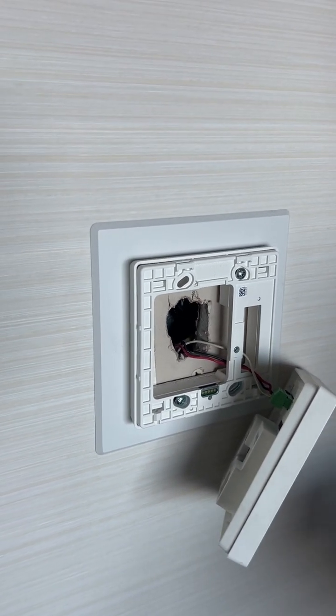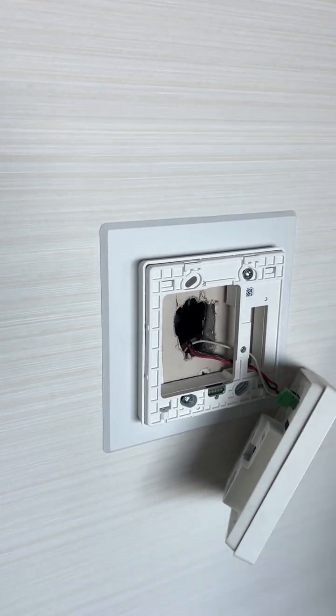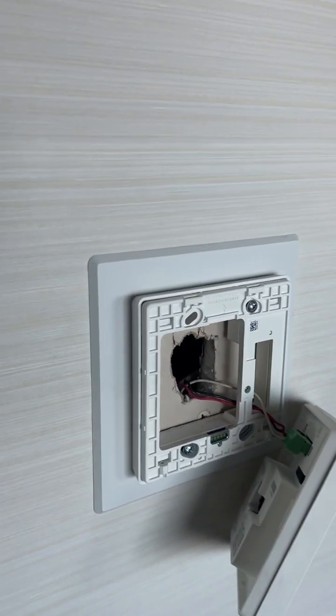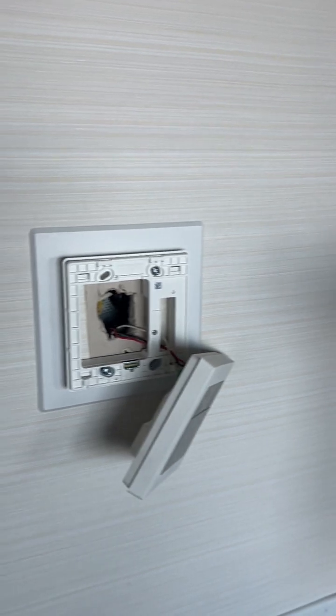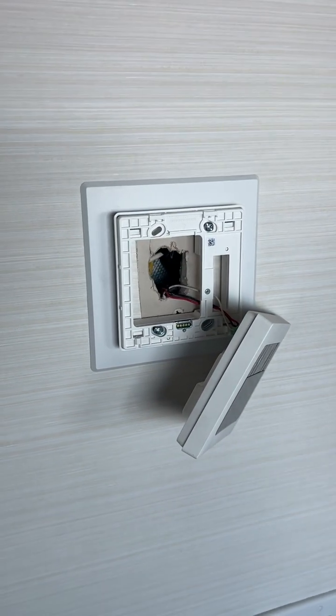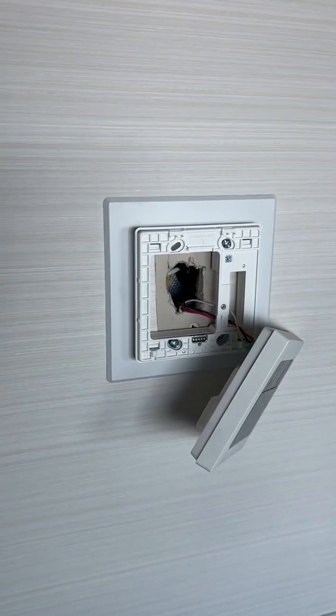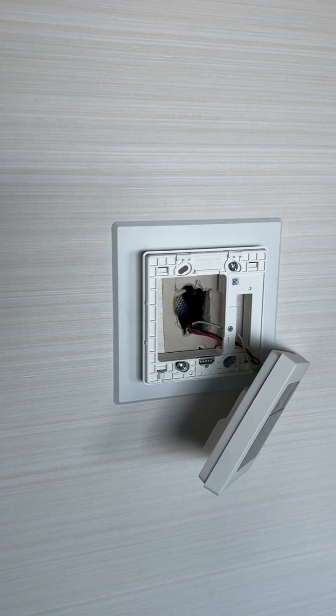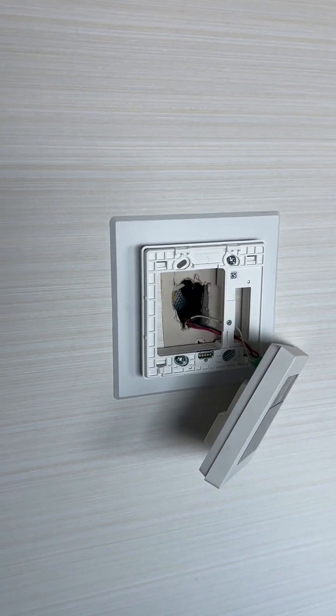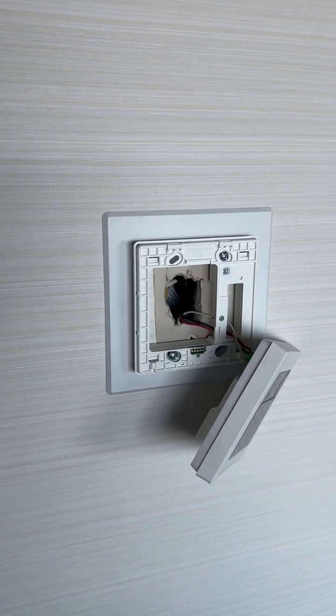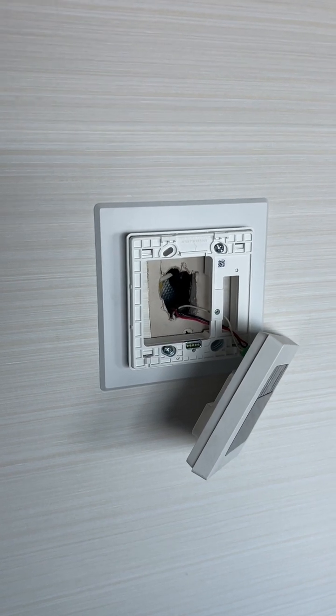Door switches and balconies, all of that - the lock you would need to rebind, because they share MAC addresses. So if you physically replace the thermostat, it doesn't have that information anymore between the lock and the thermostat. But balcony sensors, the slave relay pack, and everything else in the room will just start working.